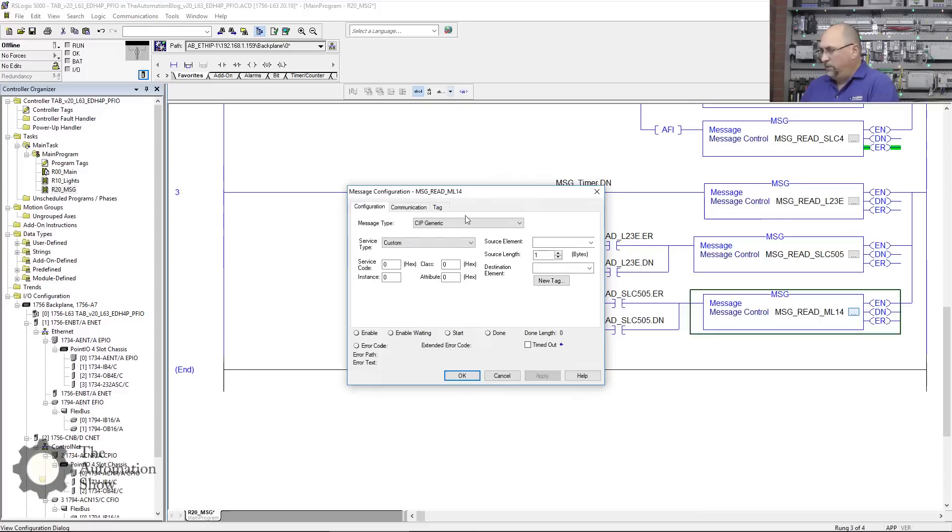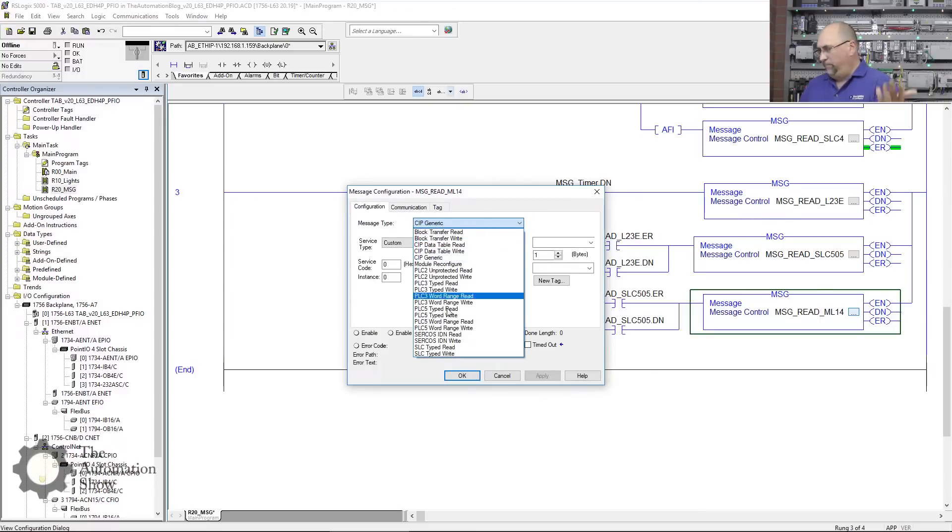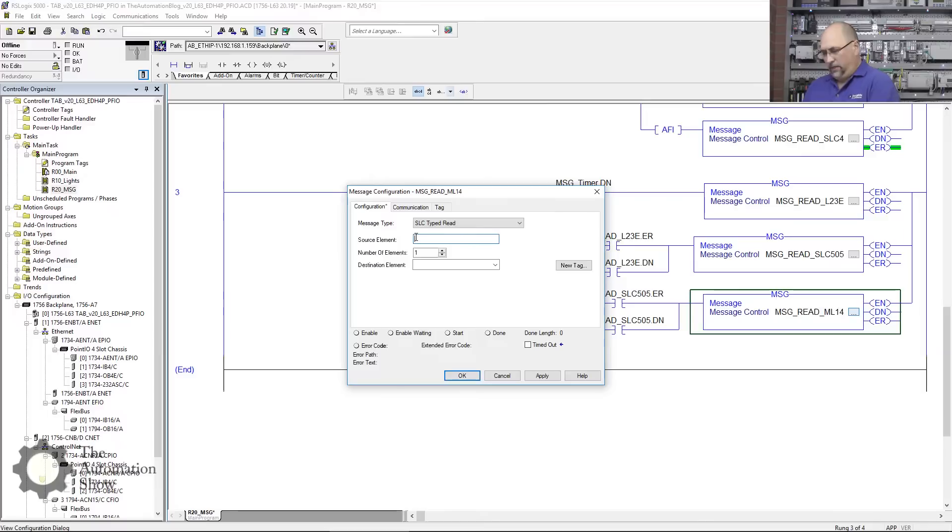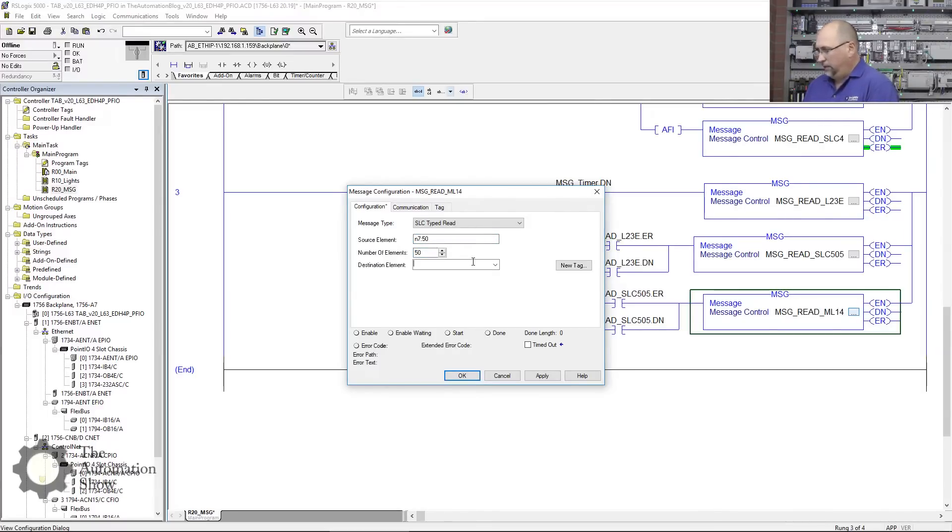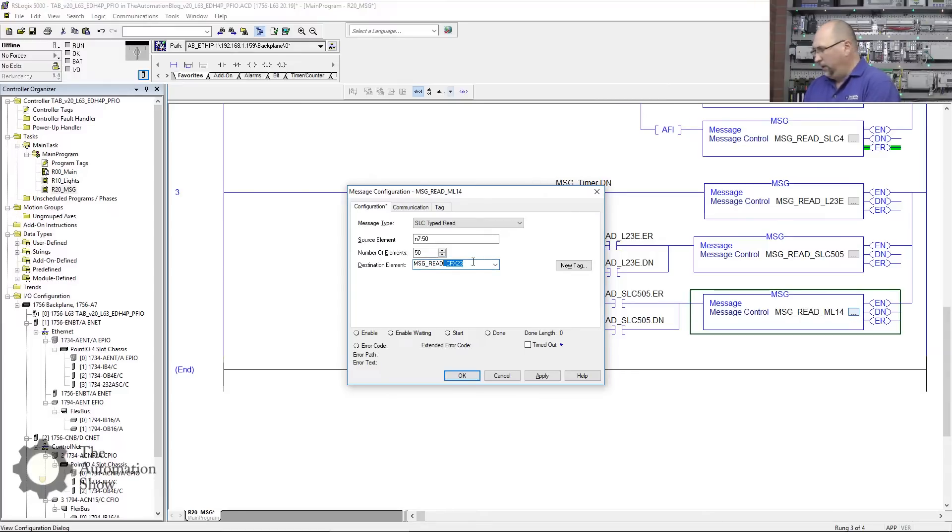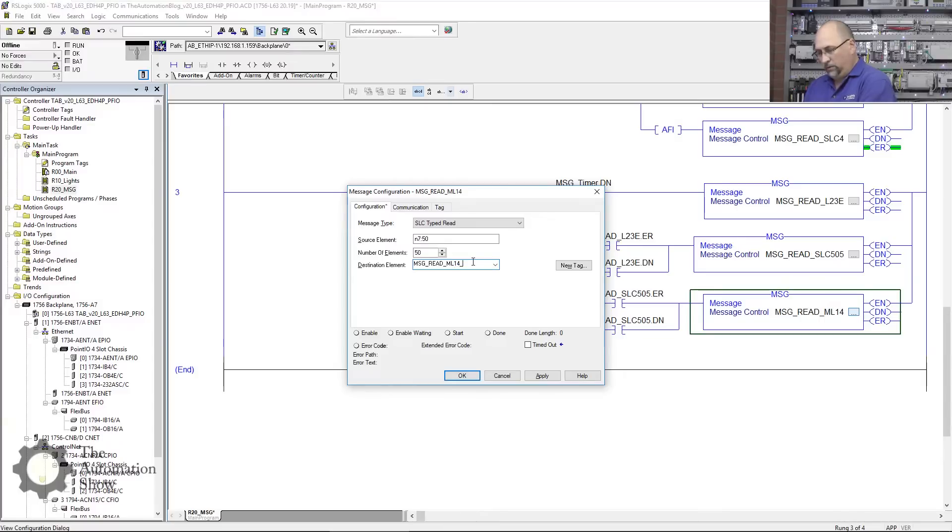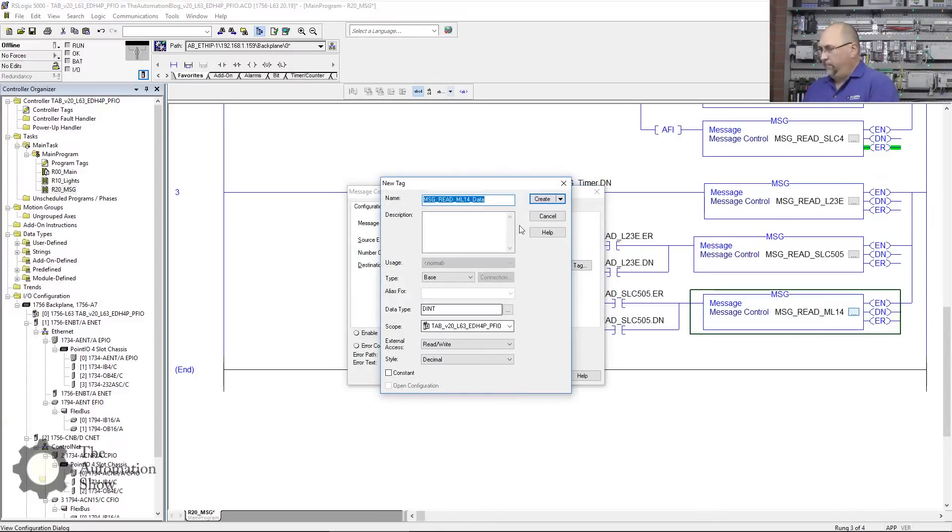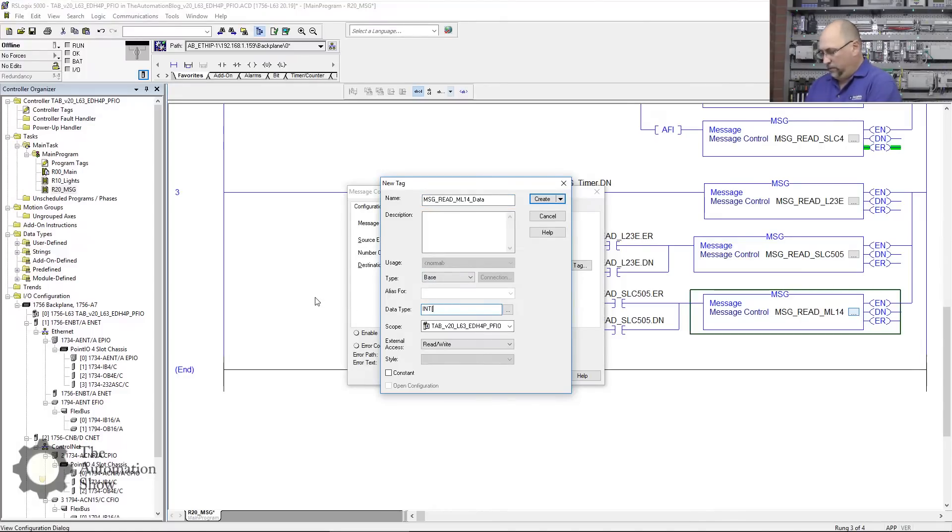In any case, let's go ahead and configure the 1400. We're going to do a—Micro Logix is like SLC 500s—we'll do an SLC Read. And again it's N7:50 because they all have the same program for my View SE course in them. And then this will be the new tag: MSG_Read_ML14_Data. New tag, and again this is going to be an INT[50].